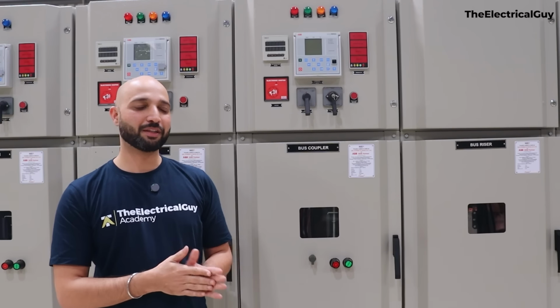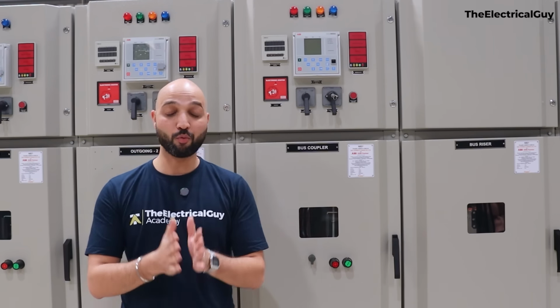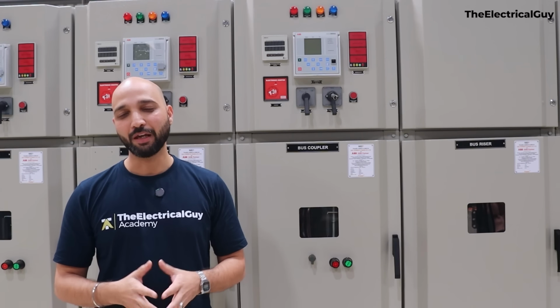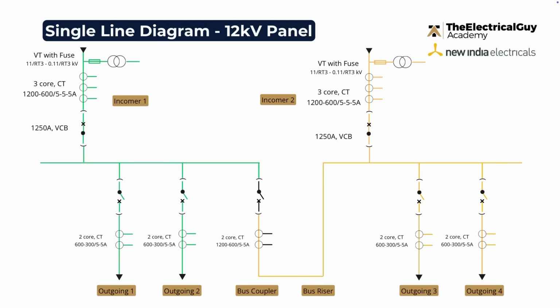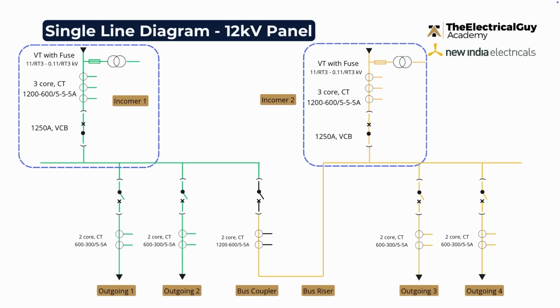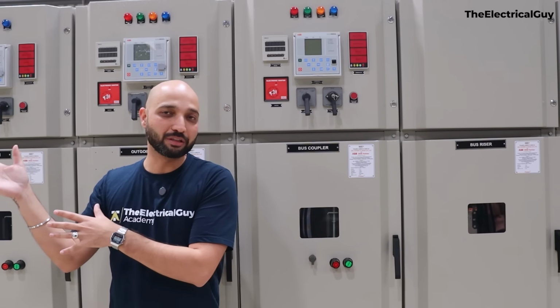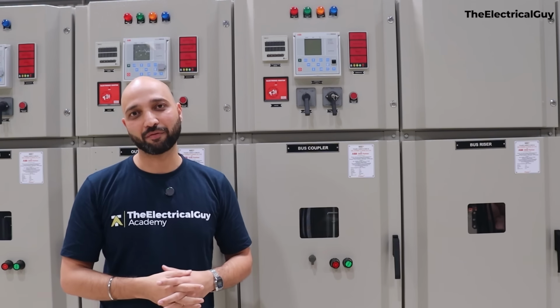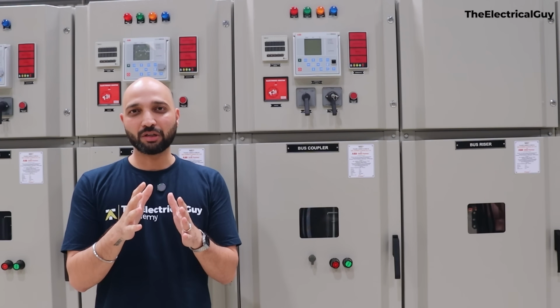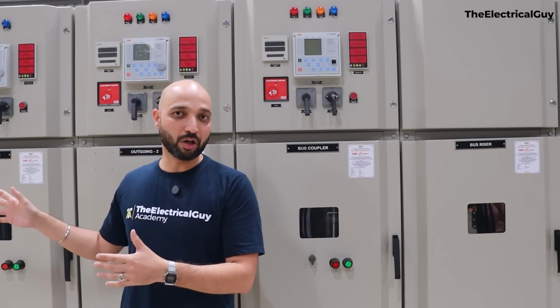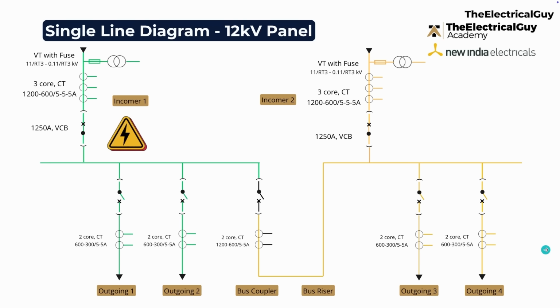Alright, so here we are with the bus coupler and bus riser panel. Now why do we need this? Let me explain that to you. So we saw we have 2 incomers in our panel lineup, Incomer 1 and Incomer 2. Now there is a high chance that one incoming is coming from, let's say, one substation, and the other incoming is coming from another substation. Now imagine something goes wrong with the Incomer panel or the Incomer 1 supply. Alright, so whatever outgoing we have connected to that particular supply or that particular panel will also lose the supply.